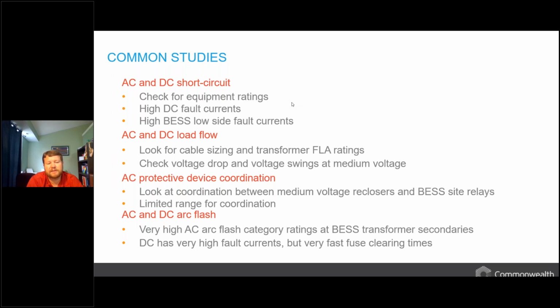We also look at the arc flash at the site. It's very important that we try to keep our workers safe when they're working around energized equipment. So we'll look at both the AC and the DC arc flash for worst case conditions. We're really trying to make sure that when workers are in and around and working on energized equipment, they have the appropriate protective equipment on for the category of arc flash ratings that exist.